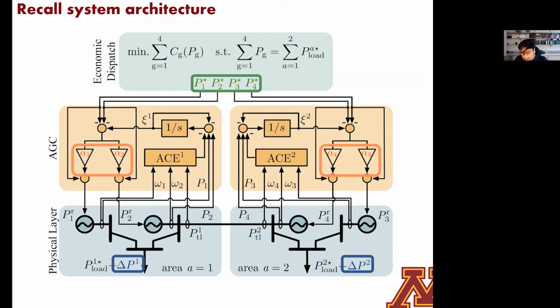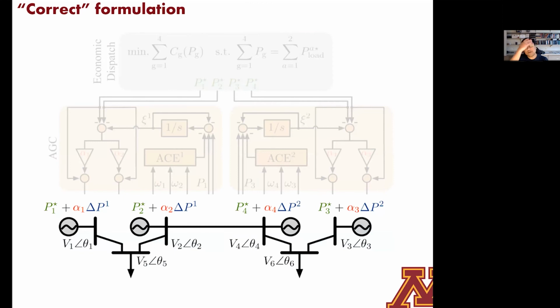And we'll try to think about what that means in the context of the power flow problem. And it turns out that the correct way to specify the power injections for all the generators is to piece all of these three pieces together and use that as the value of the real power that's going to be injected when you set up these network power balance equations. So the correct way to do this is to say that, all right, for each generator, I know that I'm going to be operating somewhere close to what my economic dispatch was telling me I should operate at, right?